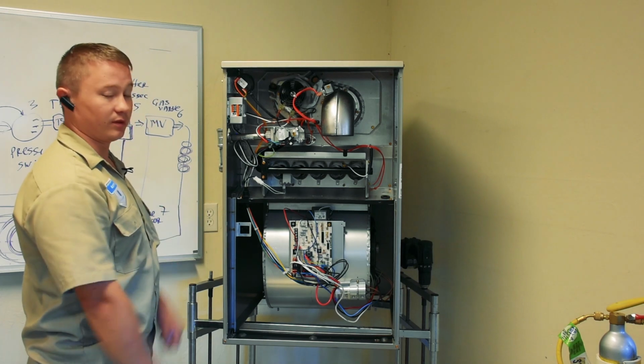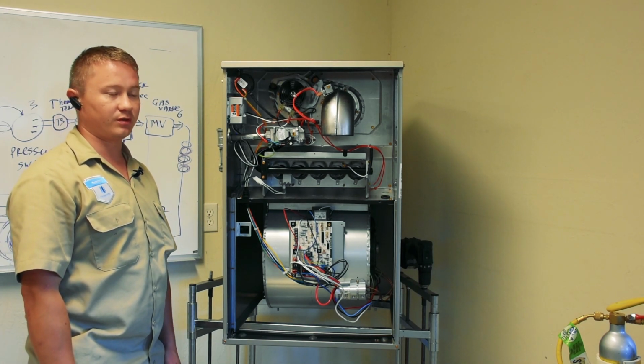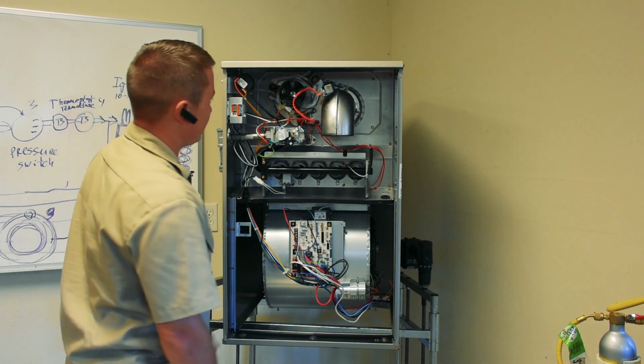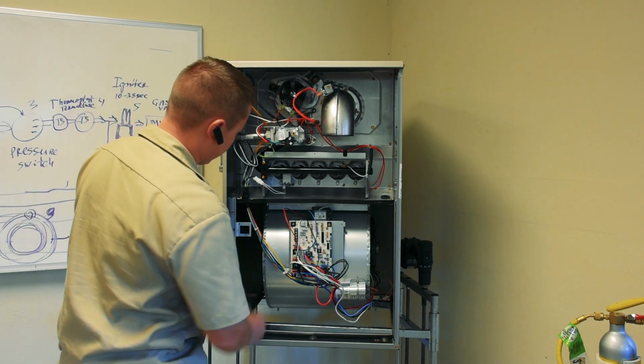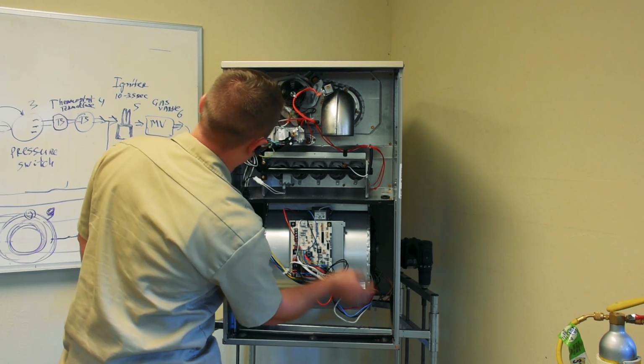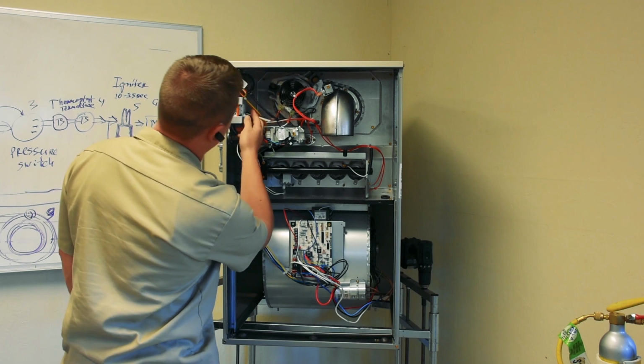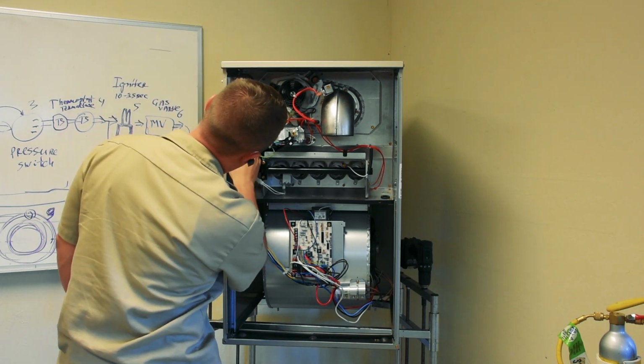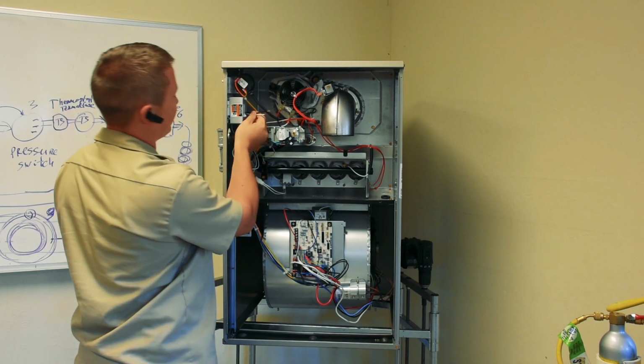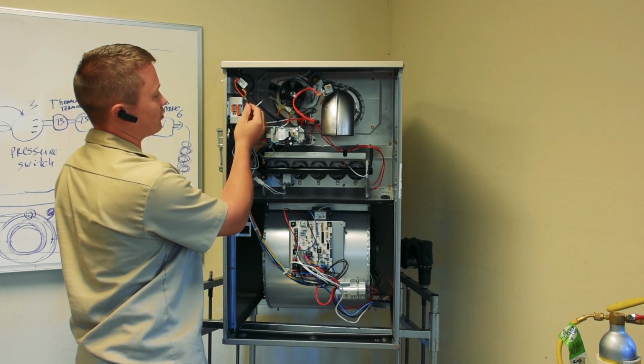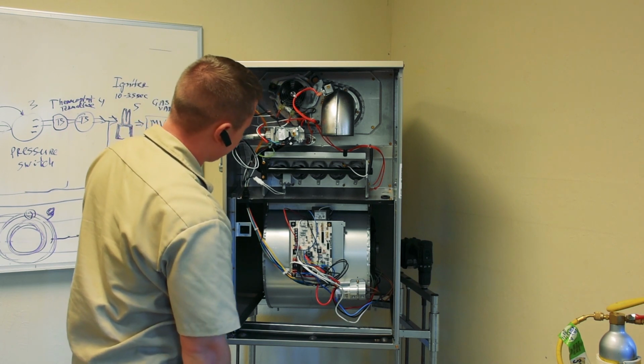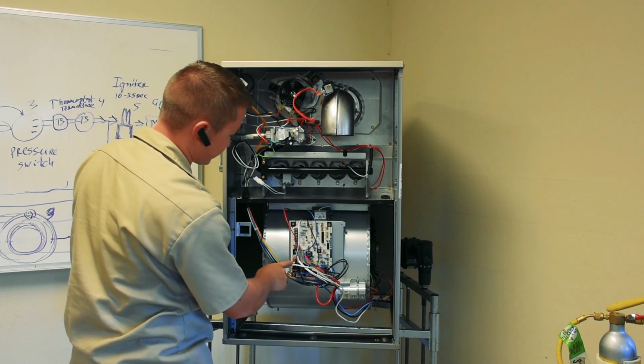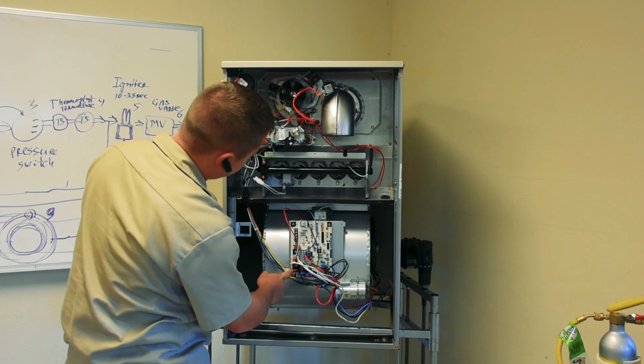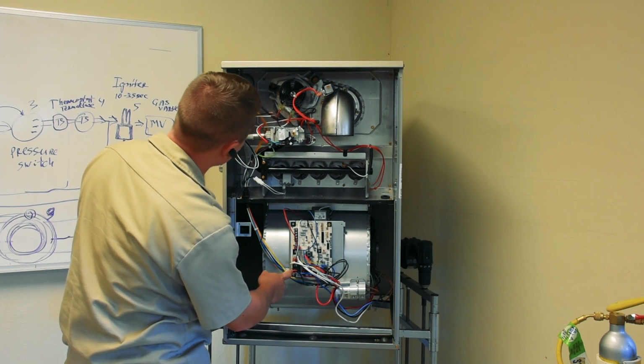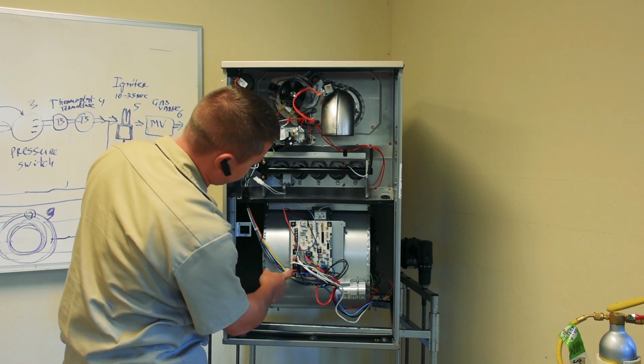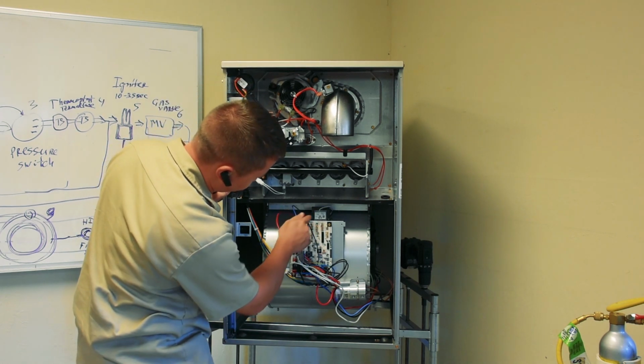Here's a half example of the furnace with ignition, like an igniter. What do we have here? We actually should have here the incoming power, two wires for 120 volts incoming power. Then these incoming wires connected directly to the control board. On the control board we have one more connector which is connected to the transformer.